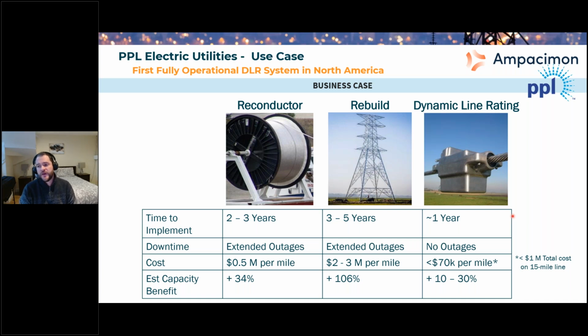We then have dynamic line rating. We're able to install this on a live line in less than a year, so there are no outages. This is where I've changed PPL's slide — PPL had 1 million as the total cost, and this particular line was 15 miles, so dividing that gives approximately 70K per mile. That's probably a bit of a high estimate; it might be cheaper in reality, but it gives a good ballpark to measure against on a common plane.